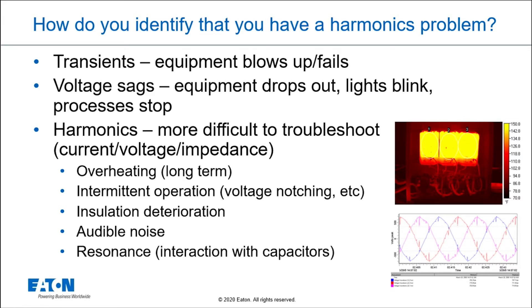Voltage sags are a very common problem. If your equipment is dropping out, it's likely a voltage sag, an interruption, or a recloser event. But that doesn't necessarily mean you don't also have something related to harmonics, because there can be misoperation of equipment with some pieces around harmonic voltage distortion. Identifying the symptoms is super important.